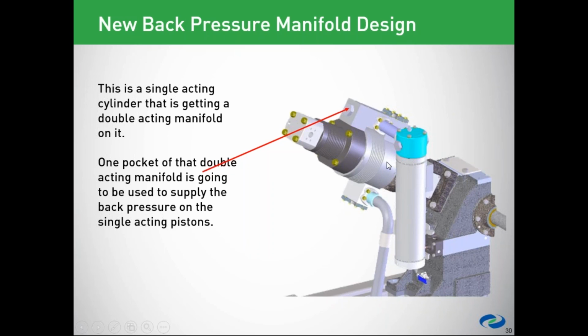So this manifold is primarily used on the first stage. Sorry. Okay, my statement is wrong. This manifold is primarily used on the lowest stage of compression. During the compression stroke for the head end, the crank end piston has a larger volume of gas, so that needs to be accommodated. So this is going to push the gas back and forth. Therefore, the extra gas volume is diverted into the inlet side of the lower stage cylinder. During the compression stroke on the crank end piston, the head end piston cannot supply enough gas to balance, that is, equalize the pressure for the crank end piston. Therefore, pressurized gas is drawn from the suction side of the lower stage to balance the crank end piston.